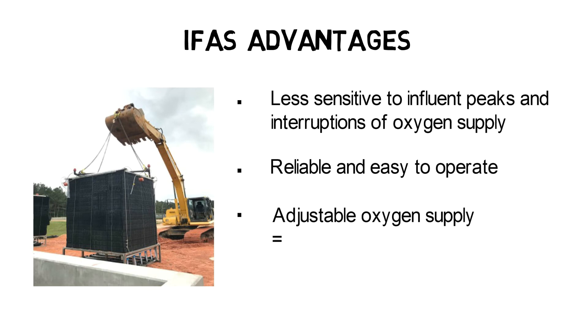Furthermore, fixed bed biofilm systems have some advantages compared to the conventional activated sludge process. The attached biofilm on the fill media surface is less sensitive to influent peaks or interruptions of oxygen supply, which makes an IFAS system reliable and comparably easy to operate. Also, the oxygen supply to the attached biofilm can be directly adjusted by the operator, or even completely automated with DO (dissolved oxygen) control.